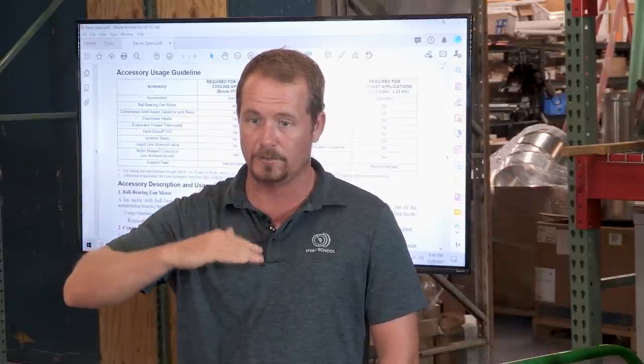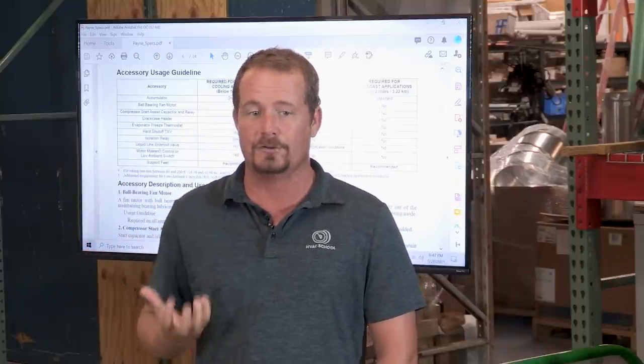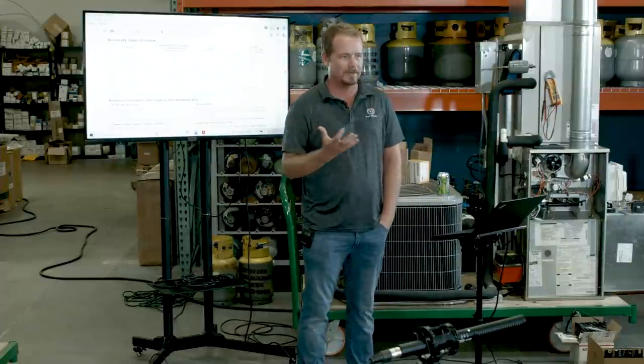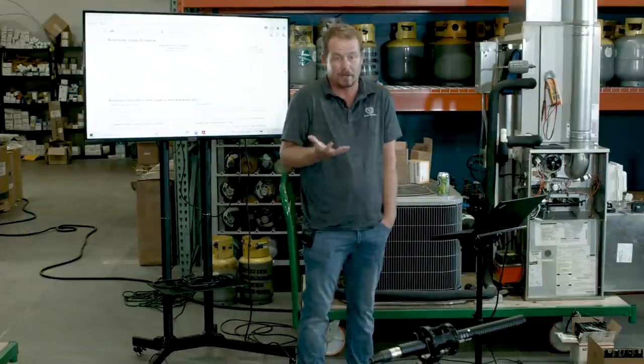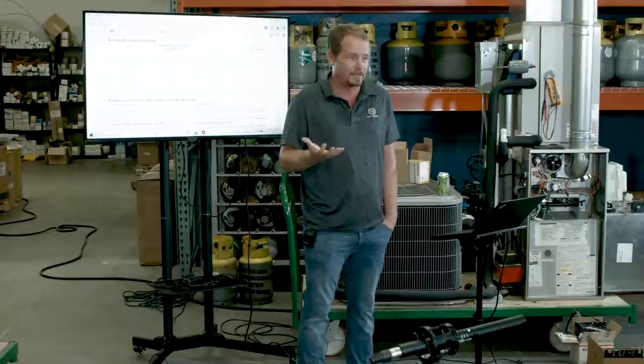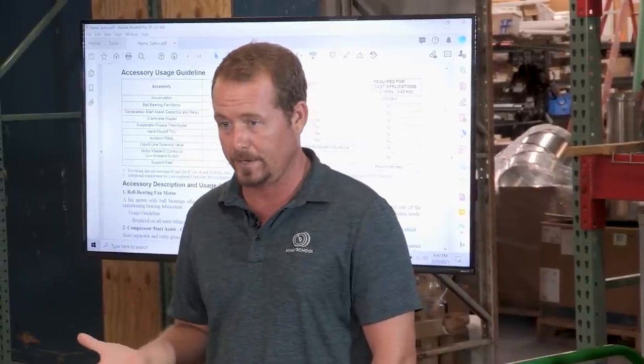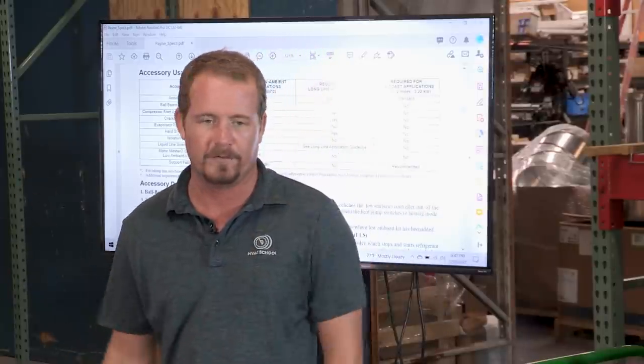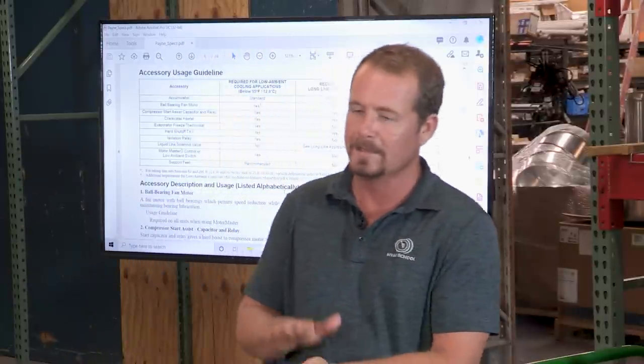The relay starts off closed, so it starts off with a lot of extra capacitance feeding the start winding. And what extra capacitance does, and whenever I talk about this I get 1,000 complaints about it because it's just not something that people talk about a lot, but it is how it works. Extra capacitance results in additional current moving in and out of the start winding. So the start winding gets more current. Because normally the capacitance of your regular 30, 40, 50, 60 microfarad run capacitor limits how much current is going in and out.